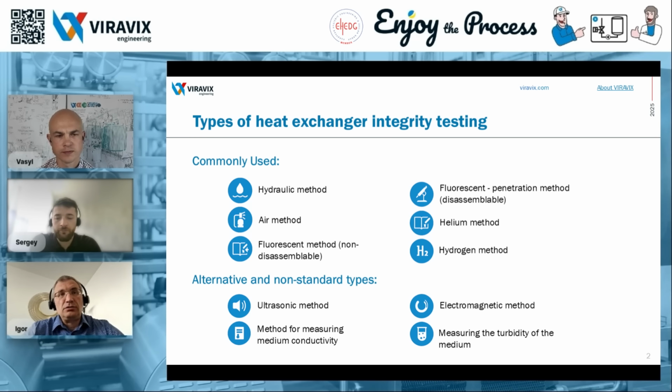Yes. In fact, manufacturers always aim to minimize costs. That's completely normal, and to continuously improve operational efficiency. So, in cases where there are no obvious signs of leakage, for example, no product contamination, the heat transfer medium, such as chilled water, is clean, and the heat exchanger is relatively new and properly maintained, then of course it makes more sense to use non-invasive testing methods.